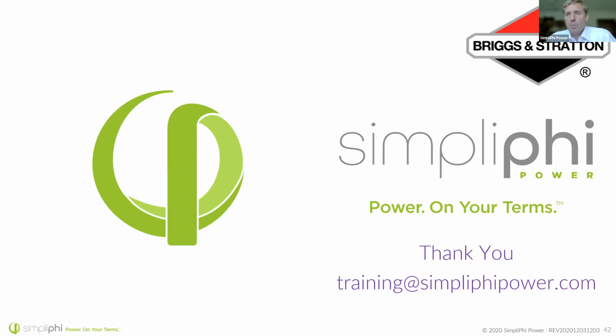Does the Phi Amplify BMS protect against freezing temperatures? Great question. The Phi battery does not. The Amplify does. The Amplify BMS monitors temperature and prevents you from charging that battery when it's below freezing. It also will allow you to discharge all the way down to -4 Fahrenheit. The Phi battery does not, and therefore you want to be careful where you locate the Phi battery. People use electric blankets or heating pads that we recommend can be used inside battery boxes. But there's another training on environmental considerations for battery installations that I would recommend you look at.